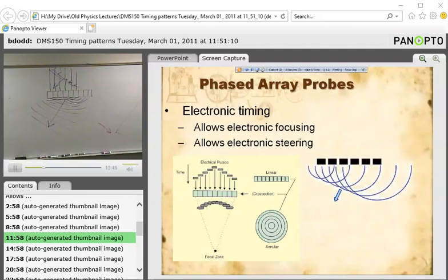Okay, so we covered that yesterday. This is how the sector scans are made today when we look at them. Typically, though, we use a different type of transducer, and so we'll take a look at how the curved ones form the image in just a minute. All right, so the other thing we can do is we can do beam focusing. We can actually focus this beam not with just the changing of the size of our crystal diameter, but we can focus it by changing our timing.